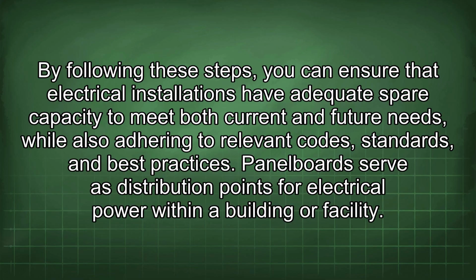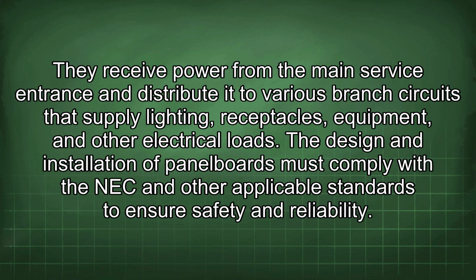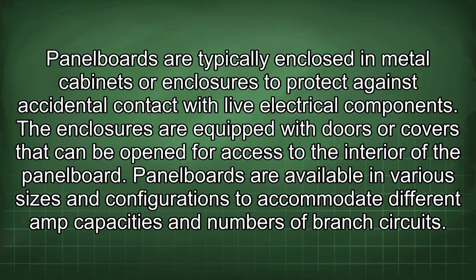Panel boards serve as distribution points for electrical power within a building or facility. They receive power from the main service entrance and distribute it to various branch circuits that supply lighting, receptacles, equipment, and other electrical loads. The design and installation of panel boards must comply with the NEC and other applicable standards to ensure safety and reliability. Panel boards are typically enclosed in metal cabinets or enclosures to protect against accidental contact with live electrical components. The enclosures are equipped with doors or covers that can be opened for access to the interior of the panel board.